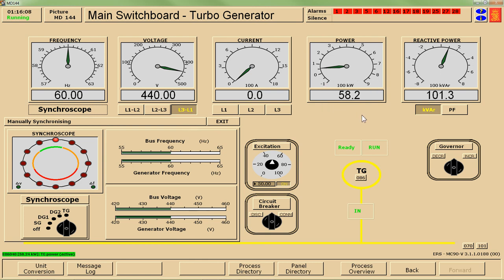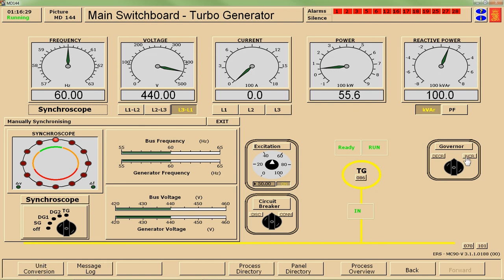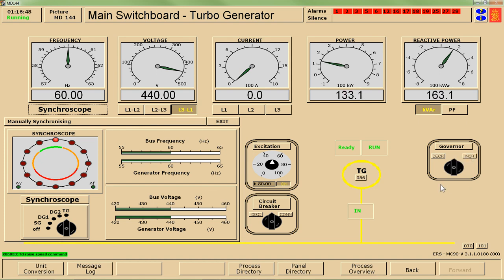My generator is now producing some power and sending it out to the rest of the electrical system. My governor now plays a different role — if I change my governor, it's no longer going to change the speed because the speed is locked. What it's going to do is allow more steam through my turbine, resulting in more or less power being produced. So if I want to produce more power, I could open up that steam valve and increase it — and you can see that our power tends to increase. That is how we go about synchronizing a generator using just one monitor.